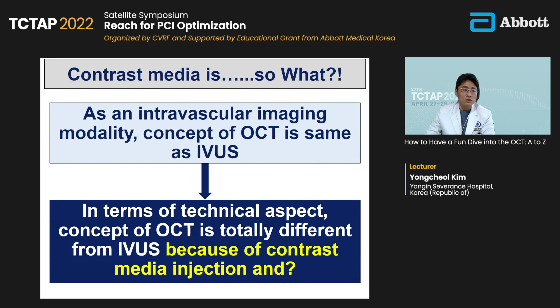and IVUS only needs you to push the pullback button to obtain the image, but OCT has further steps to get the OCT image. Step 1, press the live button for OCT activation. Step 2, press the auto calibration button for catheter flushing. Step 3, press the enable button to get ready for the OCT catheter pullback. And the final step is to press the pullback button. In addition, contrast media injection is mandatory between step 3 and the final step.